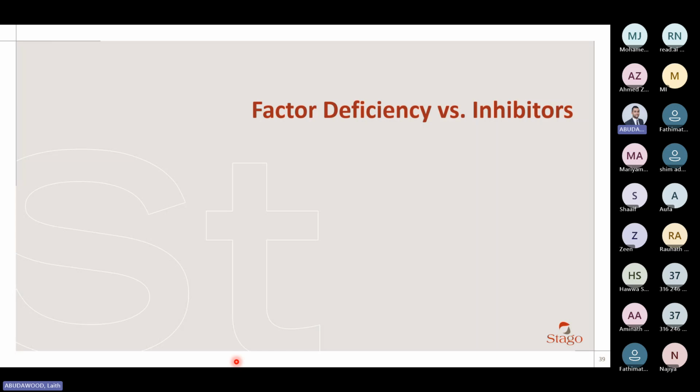If there is something that we can do, to give you a small example, for D-dimer, if there is lipemia, some studies show that you can do high-speed centrifugation, then run the sample again to remove the lipemia, and the results will be relatively accurate. But in the case of FDP, I'm not sure you can do much. And in the case of fibrinogen, I'm not sure you can do much, and the interferences are limited. So you just report things as they are. You say more than the upper reportable range, and if we think there's an interference, you just say we think there's interference. That's all we have for now as a lab.